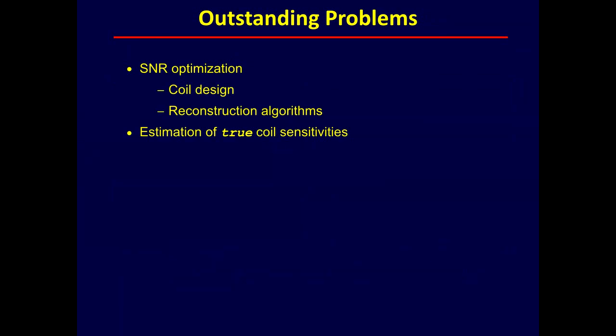You can tell that the reconstruction process, the process of inverting the matrix, really depends a lot on your coil sensitivity estimation. You want very accurate coil sensitivity, the more accurate the better, because inaccuracies in your coil sensitivity measurement are going to translate to degraded image quality or image reconstruction quality.